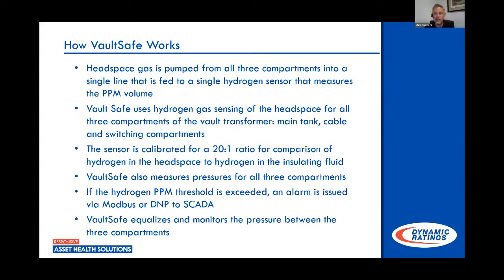So I'm taking samples of the headspace. These are gas samples, not oil samples that I'm taking. Hydrogen works a little differently when you look at it in gas as compared to when it's dissolved in oil. Typically, hydrogen runs at about a 20-to-1 ratio. Of course, it is somewhat temperature and pressure dependent, but 20-to-1 is a pretty typical number that you would see. So if you're measuring 50 parts per million in your oil, I would expect to see about 1,000 parts per million in your headspace. So you have a much greater concentration in the headspace as opposed to what you would see in oil. Also, it disperses much more quickly in the gas.